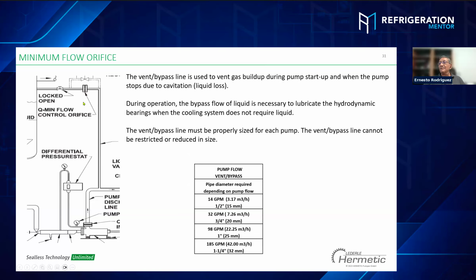Now, when you are sizing the vent line, it is where you remove all the vapor or gas bubbles generated at the pump, and also, like I said before, how the liquid returns. You can size it according to the flow of the pump: 14 gallons per minute for half inch, 32 gallons per minute for three-quarter inch, all the way to one and a quarter inch for 185 gallons per minute. You need to be careful how you size this pipe, because sometimes it is undersized.